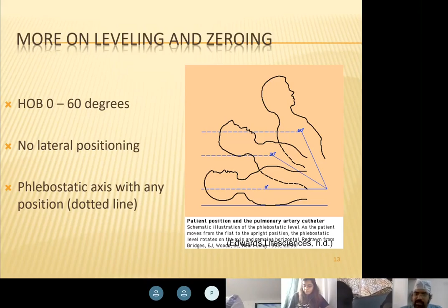Now what do these mean? If the transducer is below the phlebostatic axis, the pressure will be erroneously high. If the transducer is above the phlebostatic axis, the pressure will be erroneously low.